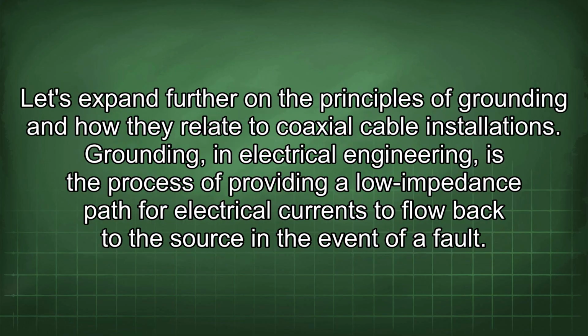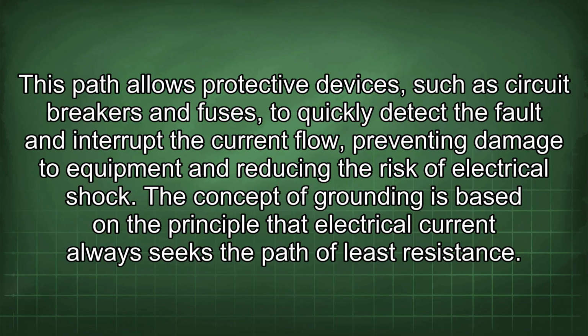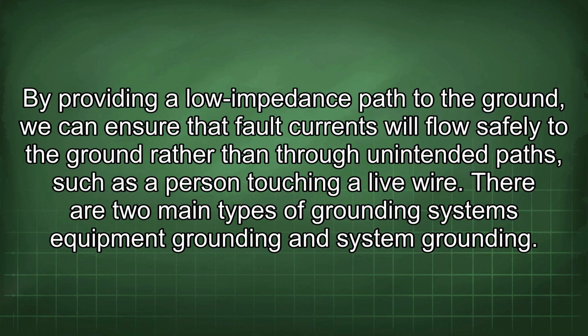Let's expand further on the principles of grounding and how they relate to coaxial cable installations. Grounding, in electrical engineering, is the process of providing a low impedance path for electrical currents to flow back to the source in the event of a fault. This path allows protective devices, such as circuit breakers and fuses, to quickly detect a fault and interrupt the current flow, preventing damage to equipment and reducing the risk of electrical shock. The concept of grounding is based on the principle that electrical current always seeks the path of least resistance. By providing a low impedance path to the ground, we can ensure that fault currents will flow safely to the ground rather than through unintended paths, such as a person touching a live wire.